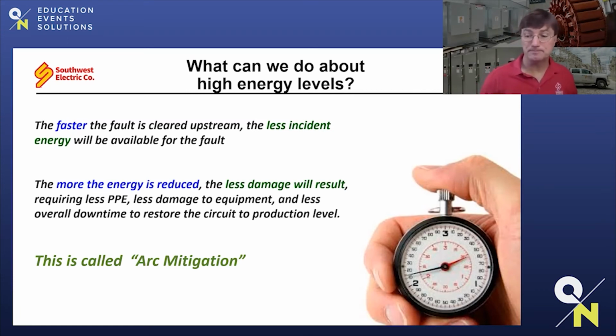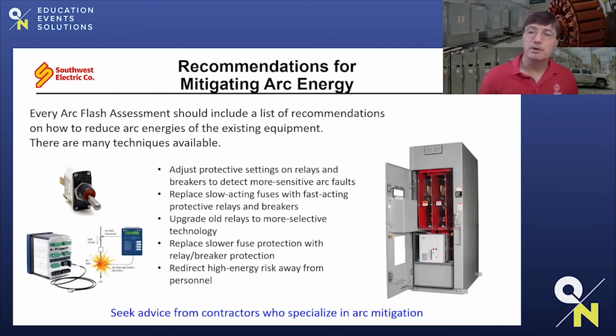All of this is called arc mitigation. There are plenty of different methods for mitigating arc energies. It can involve as simple as readjusting the settings of your current protection. It could be upgrading your current protection into something more modern and more selective. It could be upgrading your equipment altogether to have a different type of equipment that reacts to faults and is able to clear them faster than what you presently have. All of this is very complex at times, and it's certainly recommended that you talk to a third-party contractor who is experienced in arc mitigation. Southwest Electric is one of the things that we do quite often, and we would be happy to talk with anyone who wants to. But there are plenty of other contractors out there as well.